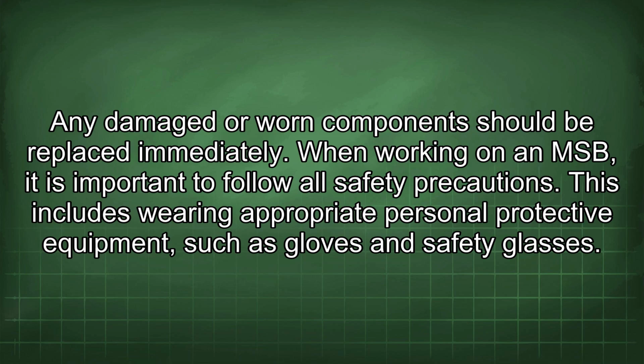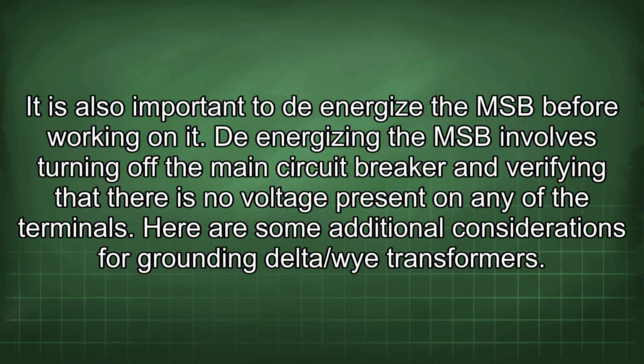When working on an MSB, it is important to follow all safety precautions. This includes wearing appropriate personal protective equipment, such as gloves and safety glasses. It is also important to de-energize the MSB before working on it. De-energizing the MSB involves turning off the main circuit breaker and verifying that there is no voltage present on any of the terminals. Here are some additional considerations for grounding delta/Y transformers.